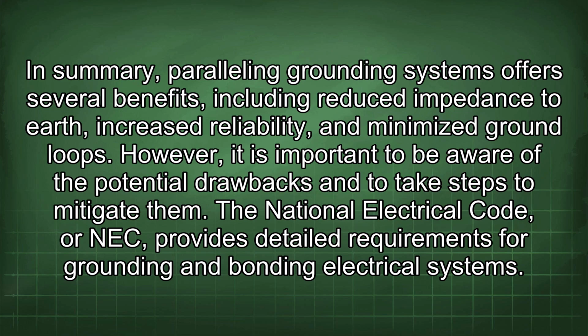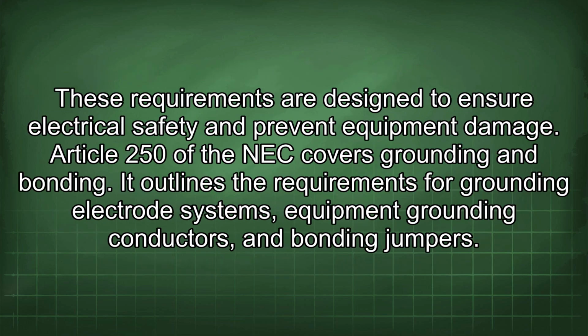The National Electrical Code, or NEC, provides detailed requirements for grounding and bonding electrical systems. These requirements are designed to ensure electrical safety and prevent equipment damage. Article 250 of the NEC covers grounding and bonding. It outlines the requirements for grounding electrode systems, equipment grounding conductors, and bonding jumpers.